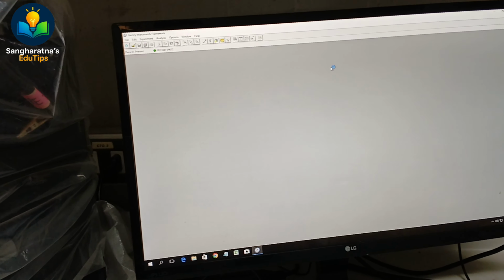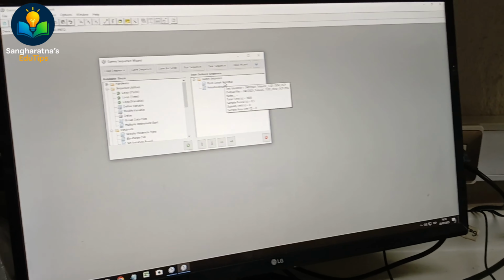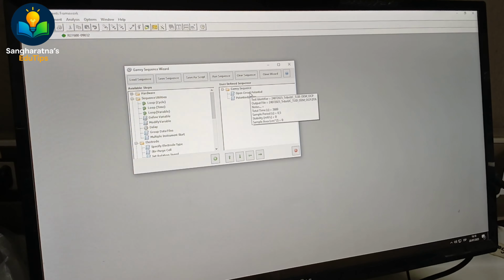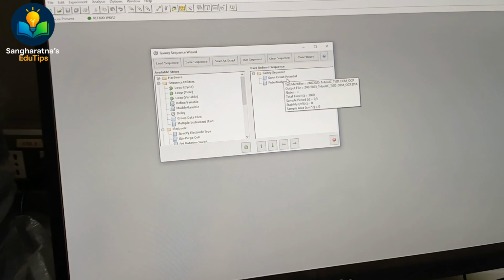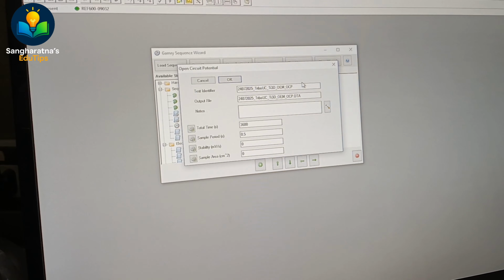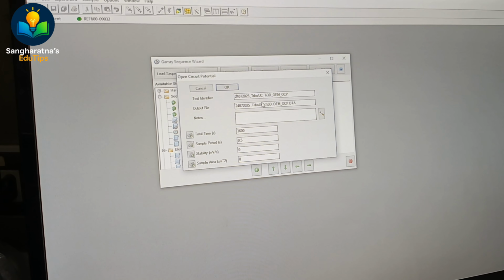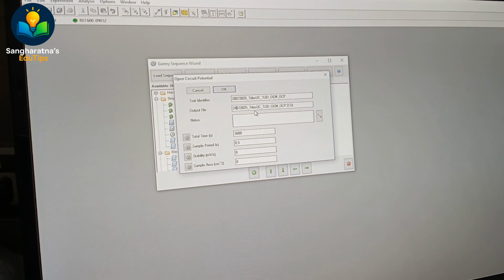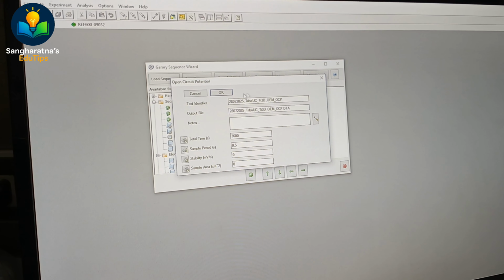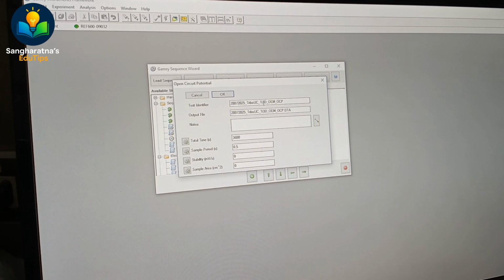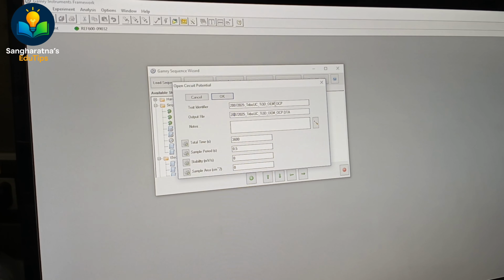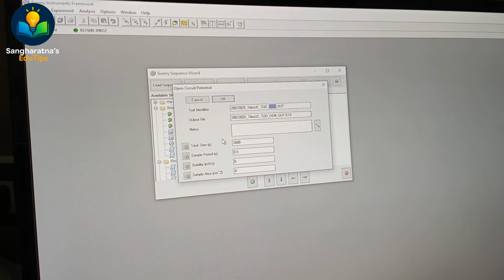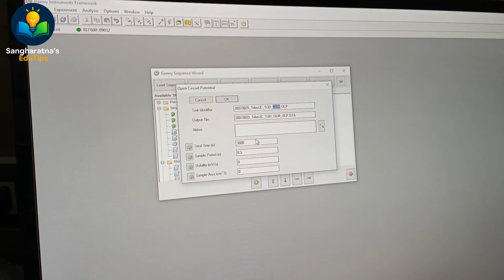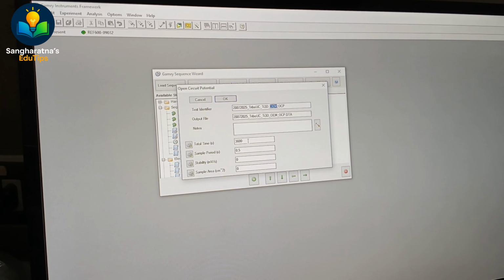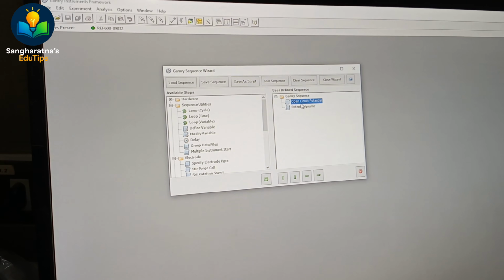So now we're gonna go again into experiment, sequence wizard, and now we're gonna check the Gamry sequence, which is composed of two tests. First of all, an open circuit potential. We're gonna double click and then check for the correct file name. We're gonna update this to the date of today, which is the 28th of July. And then the name seems to be alright because this is the OEM sample, right? Now we're going to do an OCP standardized for 3600 seconds, which is equivalent to 1 hour. We're going to say OK.